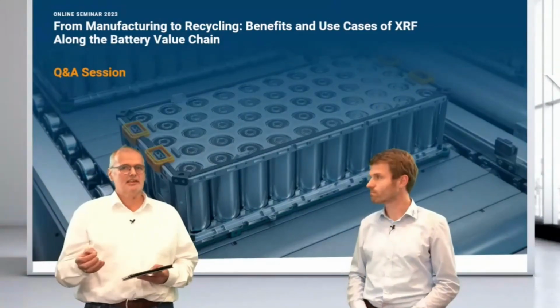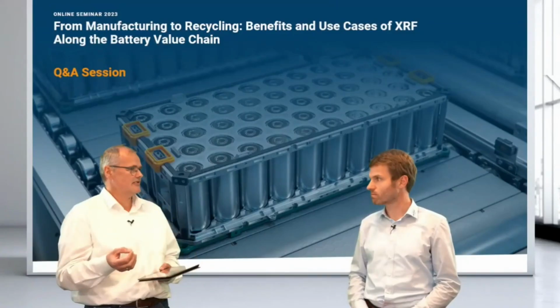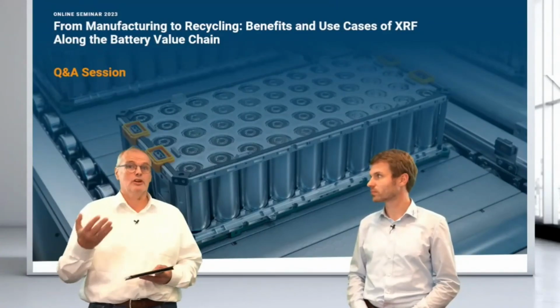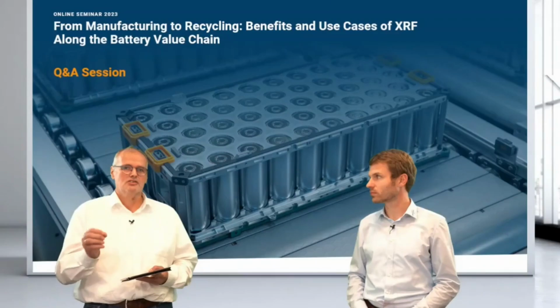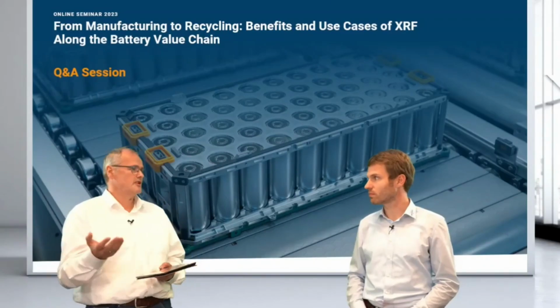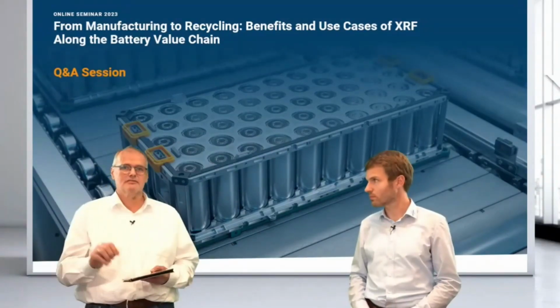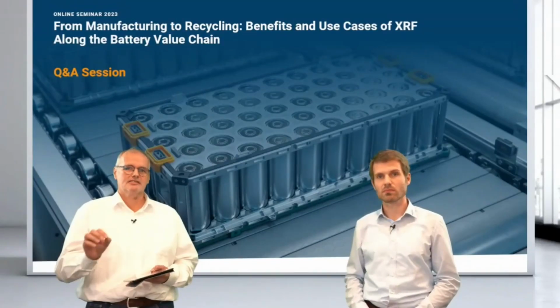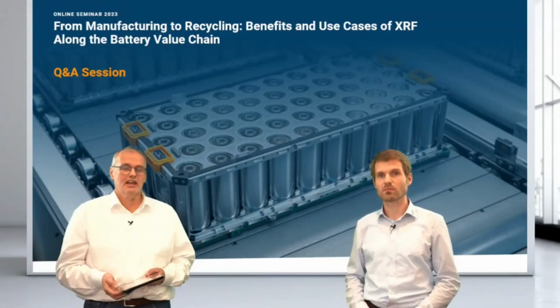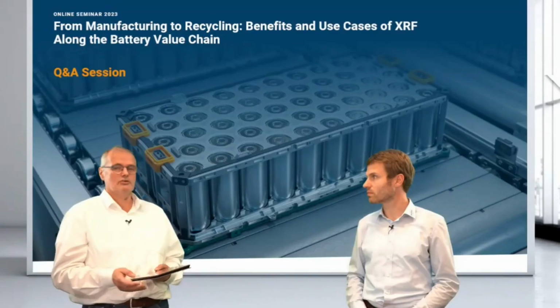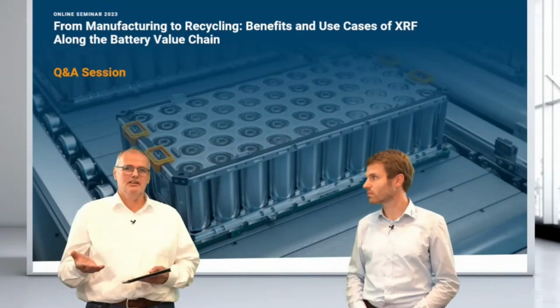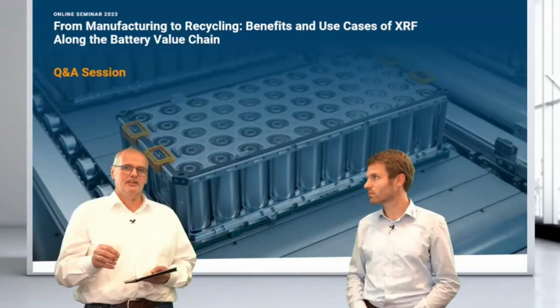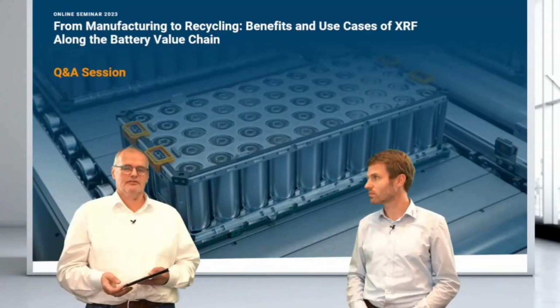The nice thing in XRF is also that there are some indicators, meaning we always look for 100% of the sample. So the missing part would be non-measurable elements, for example, and this is the so-called rest to 100. And then actually there's also a rhodium Compton signal, which is an indicator of the overall matrix of the system.